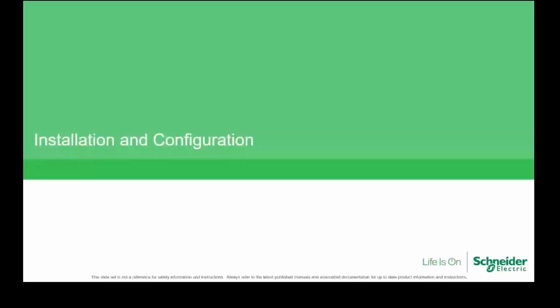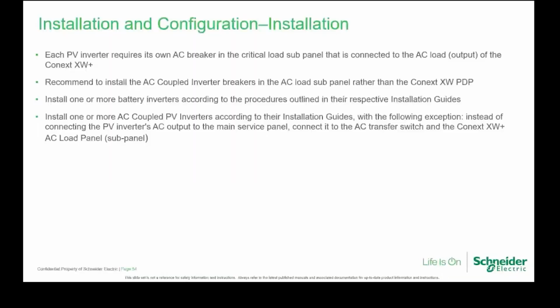Okay, just a quick look at the installation configuration requirements. Basically, each PV inverter requires its own AC breaker and a critical load subpanel. We recommend installing the AC coupled inverter breakers in the AC load subpanel rather than the Conext XW PDP. Install one or more battery inverters according to the procedures outlined in the respective installation guide. Same with installing one or more AC coupled PV inverters according to the installation guide, with the following exception. Instead of connecting the PV inverter's AC output to the main service panel, connect to the AC transfer switch and the XW Plus AC load panel.